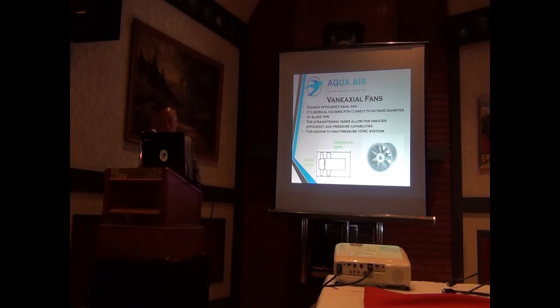Vane axial, the biggest difference, well, really the only difference for vane axial fans, is these straightening vanes here that are added. What do they do? Well, the straightening vanes allow for greater efficiency and pressure capabilities for medium to high pressure HVAC systems, and you can see it in there. The vanes just help smooth the air and build up a little bit of pressure.